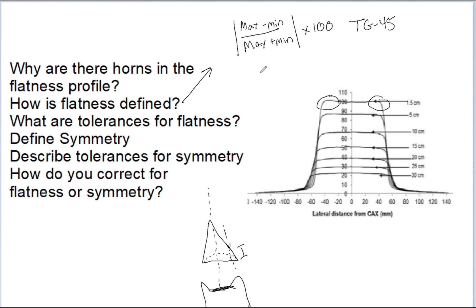You also want to ensure that the manufacturer's specifications are met. For example, Varian specs are plus or minus 2.5%. NCRP says they can be within 3%. Since my clinic has Varian machines, we are going to use that 2.5% because it's more strict compared to the NCRP. We use 2.5% for our tolerance.